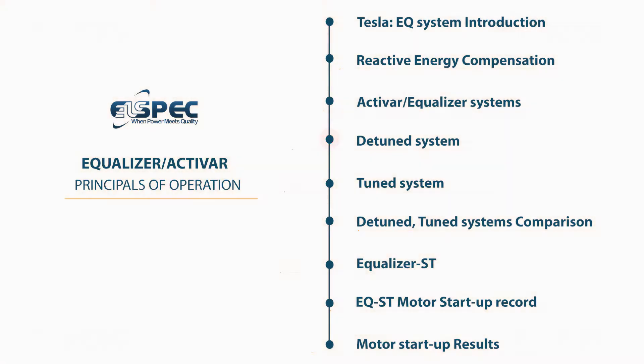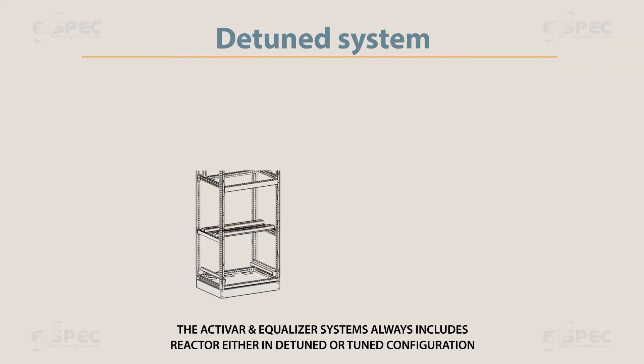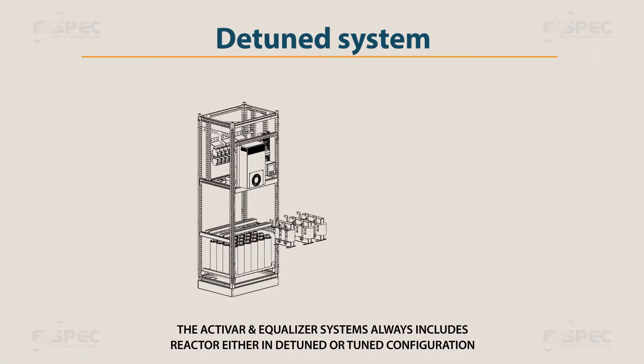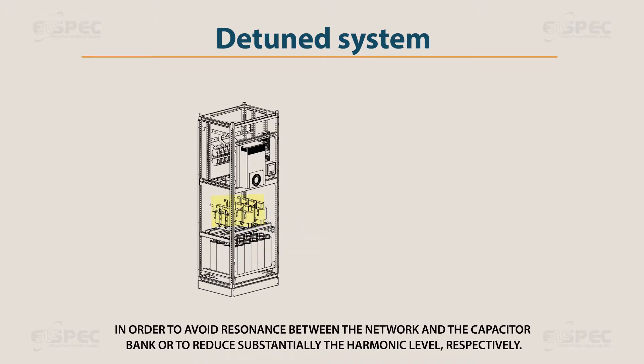The ACTIVAR and equalizer systems always include a reactor, either in detuned or tuned configuration, in order to avoid resonance between the network and capacitor bank, or to substantially reduce the harmonic level respectively.